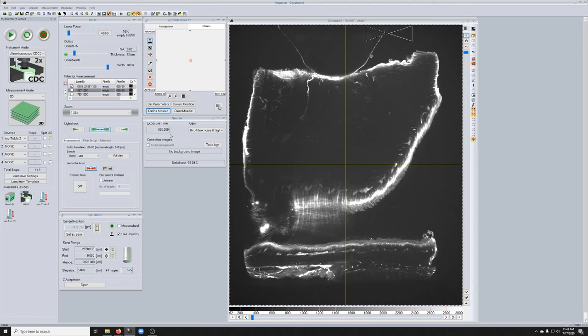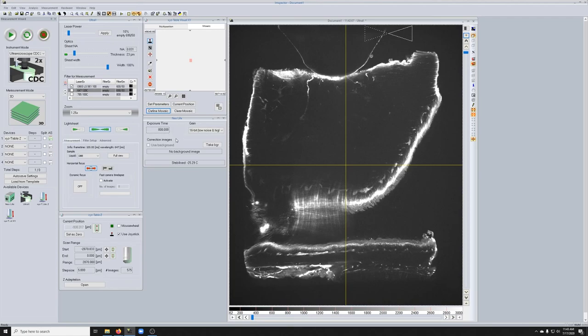When we're taking a Z stack, we want to minimize time. Bleaching is not such a huge concern in light sheet because you're only illuminating what you're looking at, and if you illuminate it very briefly, it tends not to be a problem. We want, if possible, to lower the exposure time as much as we can, but get the same quality by increasing the laser power. How do we balance these things?